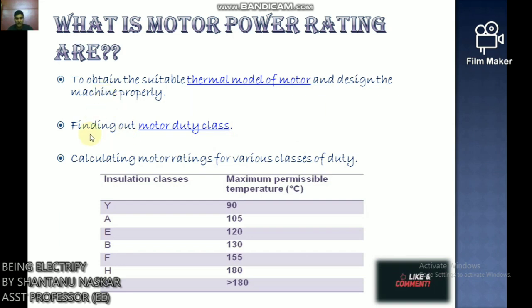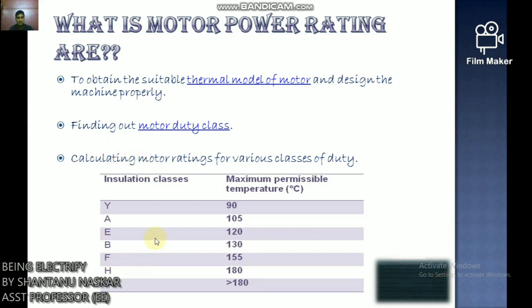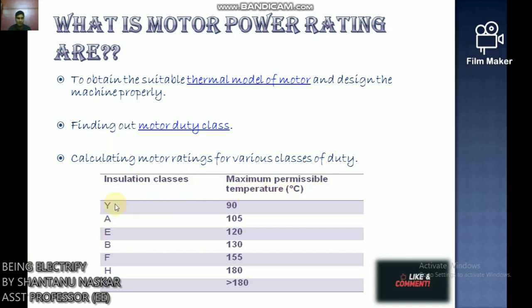The main objectives of selecting motor power rating are: number one, obtaining a suitable thermal model and designing the machine properly; number two, finding out motor duty class; and number three, calculating motor rating for various classes of duty. Insulation classes with maximum permissible temperatures are: Y (90°C), A (105°C), E (120°C), B (130°C), F (155°C), H (180°C), and C (greater than 180°C).